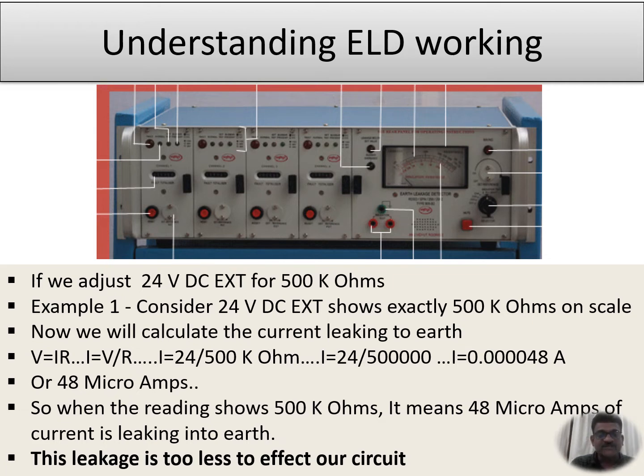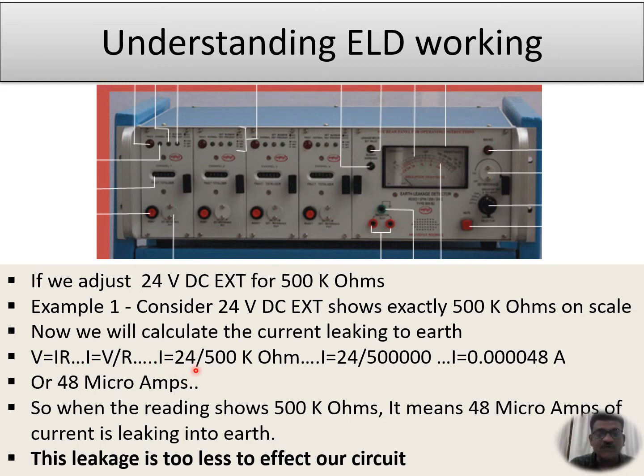Let us take two examples. If we adjust 24 volts external for 500 kilo ohms — what does it mean? Consider 24 volts external is exactly 500 kilo ohms on scale, showing a leakage resistance of 500 kilo ohms. Now if we calculate the current leaking to earth using V = IR, which gives I = V/R = 24 volts divided by 500,000 ohms, we get 48 microamps.